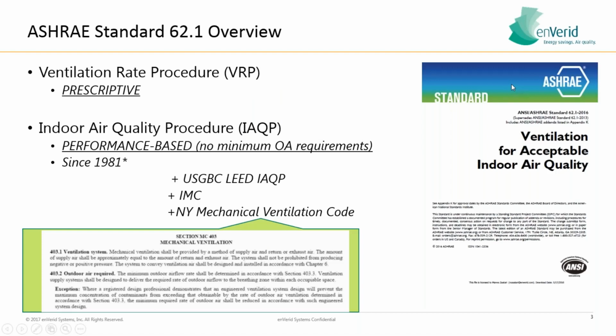So ASHRAE 62.1, just for those who might not be really wonked out on ventilation requirements for large commercial buildings, there's essentially a few different procedures that are done to calculate how much outside air you need to bring into a building. The one that most folks are familiar with is the ventilation rate procedure. It's a certain number of CFM based on space type, occupancy, square footage, etc. There's nice tables in ASHRAE that show how much outside air you should bring in, and then that is used to flush out contaminants from within the building.